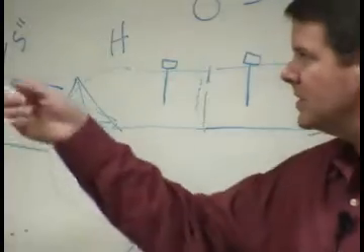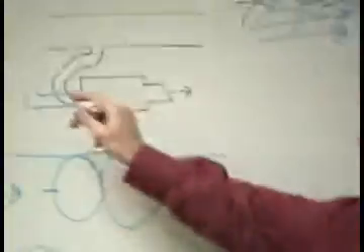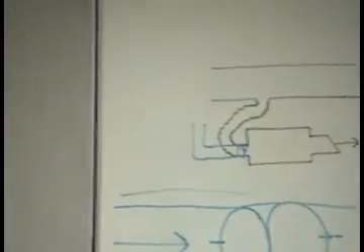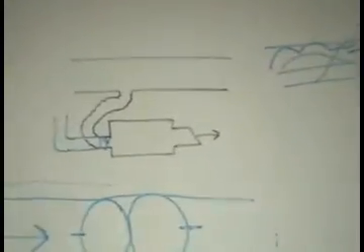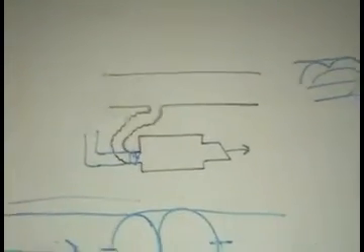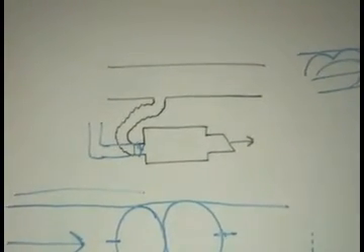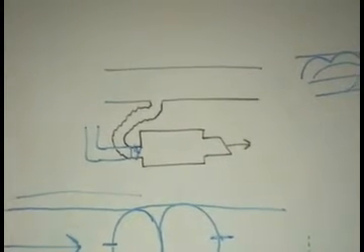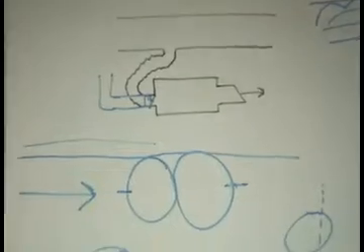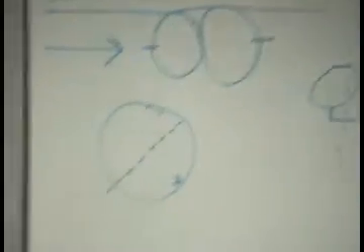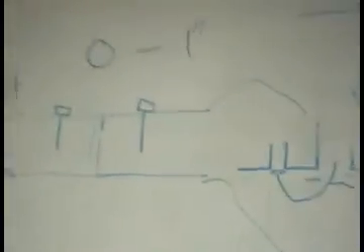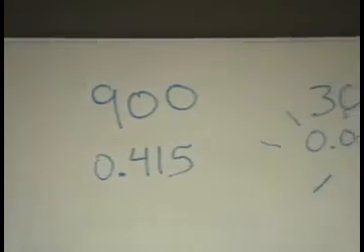A lot of these manufacturers will come with the pitot coming off of them, and they'll have little plastic T's with a plug in the T, so that when the balancer comes along, he can take those plugs off and plug his meter in there and see what the differential is across it. I see those things crack or split, or the little rubber plug in the T falls off or gets old and deteriorates and falls away. I just cut them out. I would just remove those. Get rid of them now. We have enough trouble with CFM. We don't need any help.